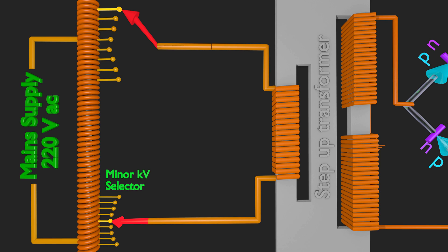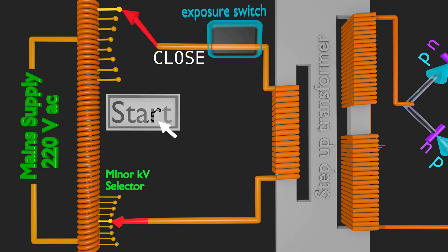Next circuit element is exposure switch. Exposure switch turns on and turns off X-ray exposure. Electronic devices like silicon controlled rectifiers and vacuum tube triodes are used for switching X-ray KV circuits. When operator clicks on or presses start button at control console, the exposure switch closes to allow electricity to flow in the KV circuit and exposure starts. So, operator starts it manually.